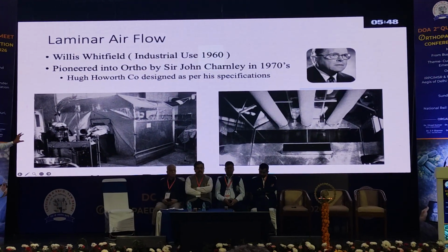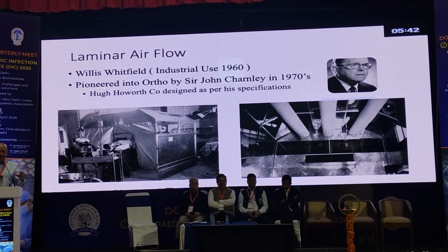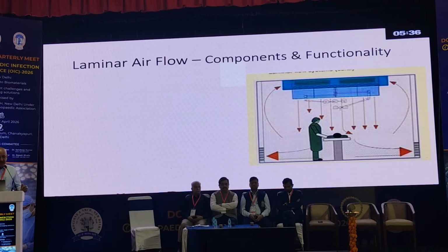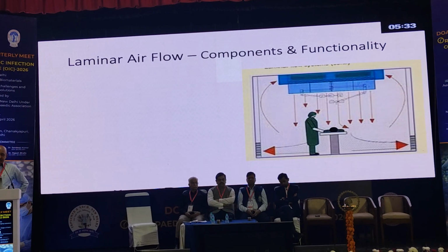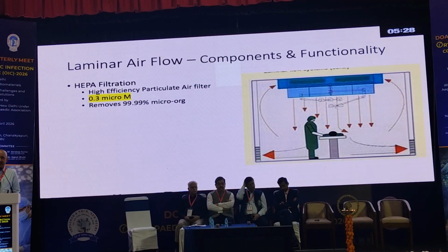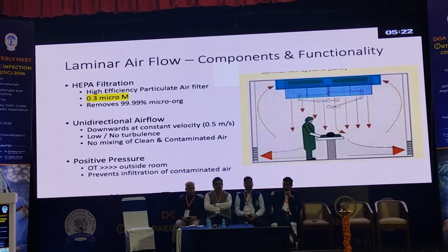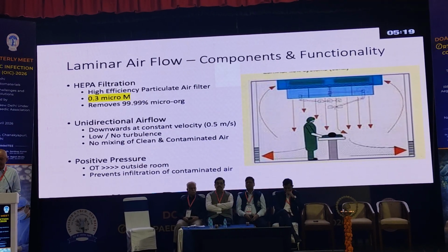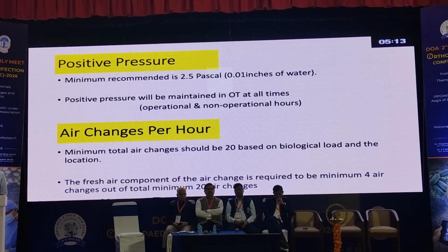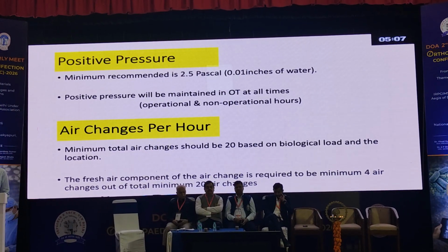So he made this first attempt to transport the laminar flow system. It was a very, very sort of a makeshift arrangement, and he found that if you are using a HEPA filter and you are trapping the very, very small bacteria, viruses, you are also having a unidirectional airflow and you are having a positive pressure air from the OT moving outwards. This should help reduce your infection rate. So this was the recommended value for the positive pressure, and this is the value for the number of air exchanges per hour.